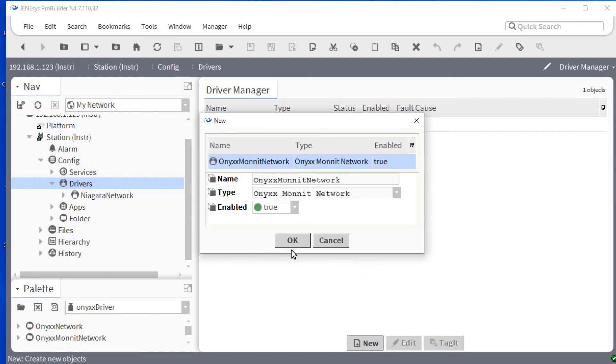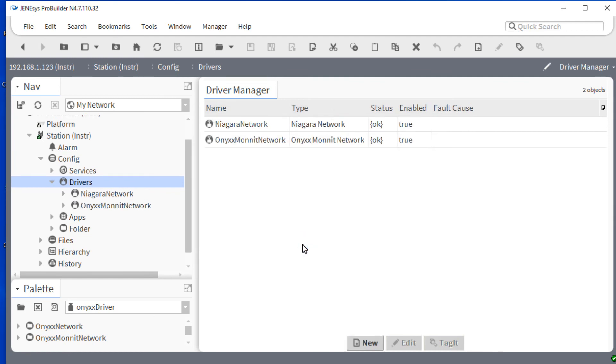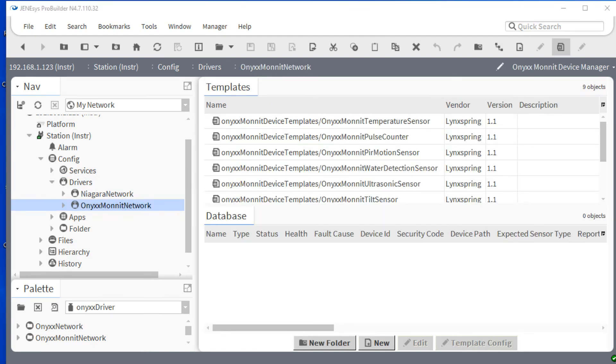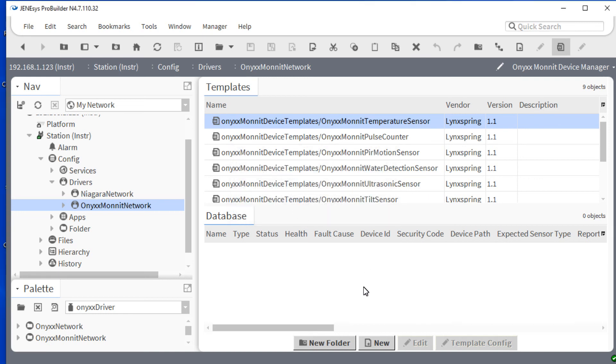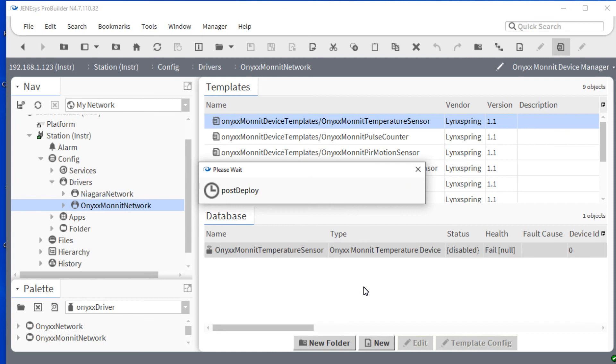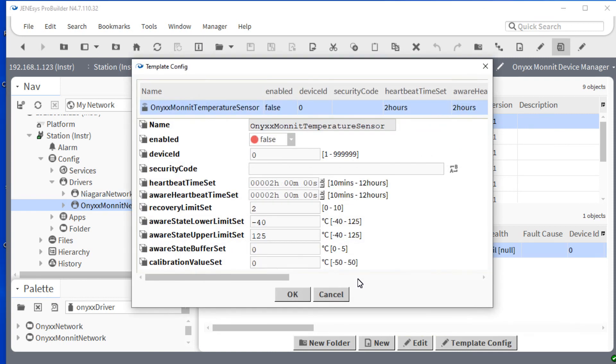When you add it, you may choose to change the name if desired. Once you have added it, you will want to return to the nav tree and double-click on the Onyxx Monnit Network. Once you are inside the network, you can select the appropriate template and drag it into the database at the bottom of the screen. This will bring over the information necessary to configure the particular device. You will need to ensure that you have enabled the device as well as adding the device ID and security code located on the side of the device.